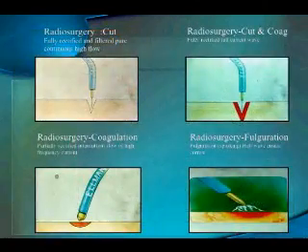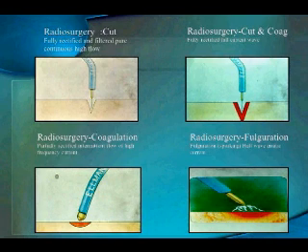The filter cut, which is 90% cutting and 10% coagulation, produces micro-smooth cutting and is mainly used for skin incisions, biopsies, and grafting. The cut and coag, which is 50% cutting and 50% coagulation, is mainly used for endonasal DCR, transconjunctival blepharoplasty, and excision of verrucae and nevi.